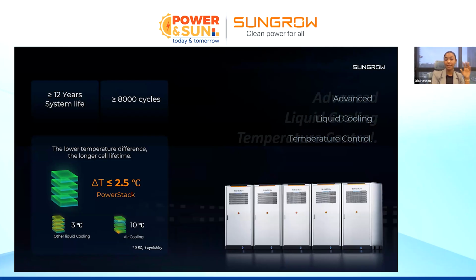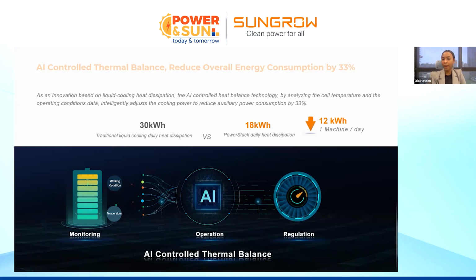But the liquid cooling on the other side, it's AI powered. So it actually checks the realistic energy storage system temperature and activates itself accordingly and regulates its temperature according to the battery racks themselves. It will also ensure that the battery cells do not have more than 2.5 Celsius in terms of cell temperature difference. Because the higher the cell temperature difference, the lower is my efficiency. And most probably my system will follow that cell with the least performance, so that will bring the whole rack performance down. So with the AI-powered liquid cooling application, it actually reduces your electrical consumption when it comes to cooling by almost 33%, because it's AI-powered and it regulates its temperature according to the battery rack and battery cell temperatures themselves.